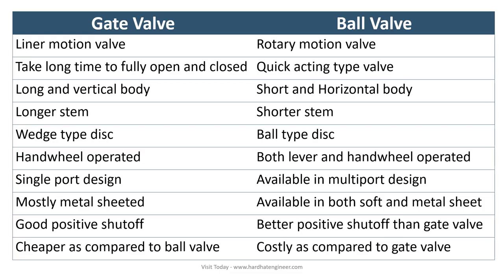These are the main differences between the gate valve and ball valve, summarized on this slide. Both gate and ball valves are the right choice for positive isolation. The ball valve offers a slightly superior shutoff as compared to the gate valve due to its soft seat design. Choosing the correct valve for your service depends on many factors such as cost, fluid of the service, temperature, pressure, and life cycle of the plant.